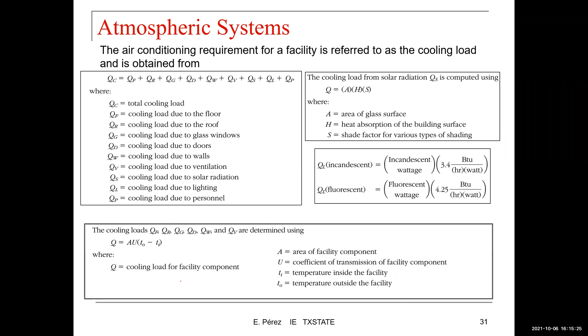But the cooling load for solar radiation is computed using this formula, in which we multiply the area of the glass surface times the heat absorption of the building surface times the shade factor for various types of shading. Also, for the lighting, QL, we will look at the type of lighting used in the facility. If it is incandescent, we use this formula. If it is fluorescent, we use this formula. And once we get each piece, we can add them all, and that will be the cooling load for the facility.